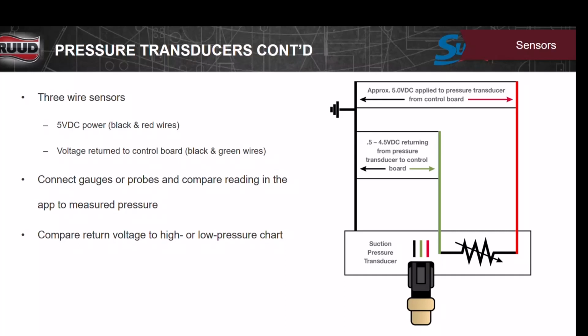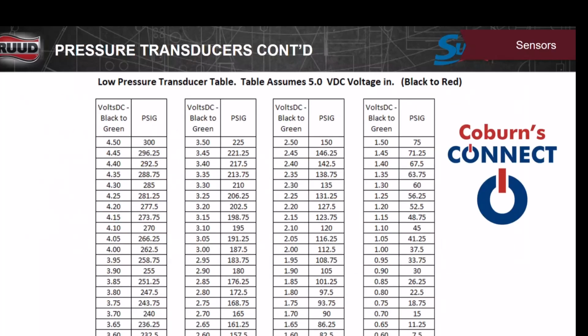Between the 3 wires, you're going to go from the black and the red wire. The red wire is going to be your power. You should have 5 volts DC there. Between the black and the green wire, you'll have anywhere from 0.4 to 4.5 volts, depending on the pressure that's in there. Here's what the chart looks like. So if we're seeing 2 volts on green and black, we're approximately 112 psi. I was reading this, but I was actually up here. But the pressure transducer was telling me different. So that's how you can tell if you got a problem.